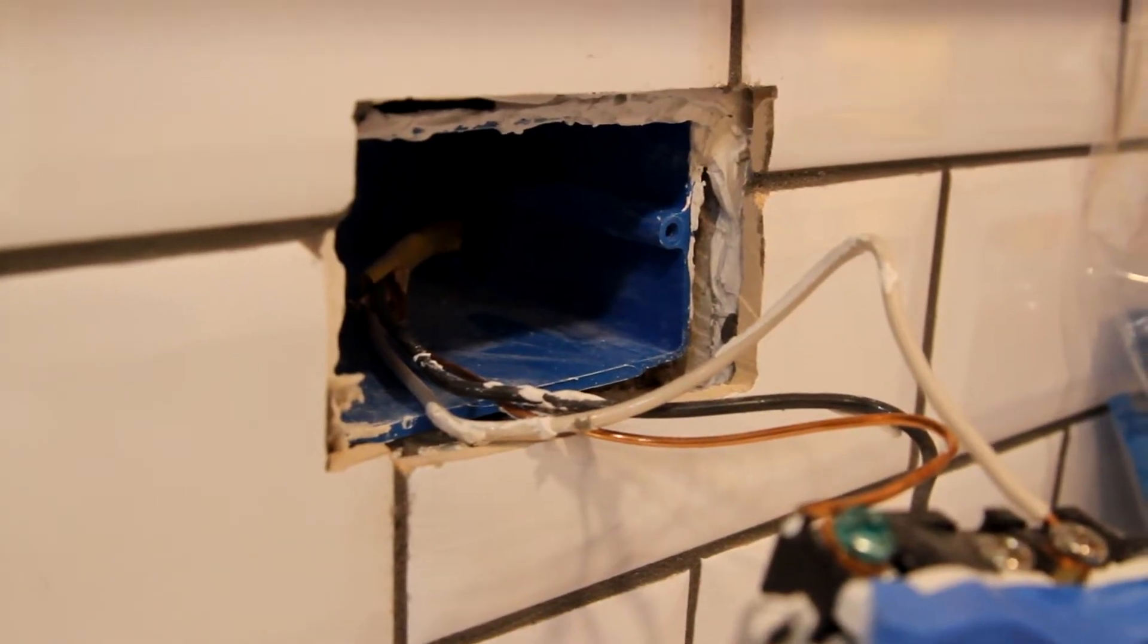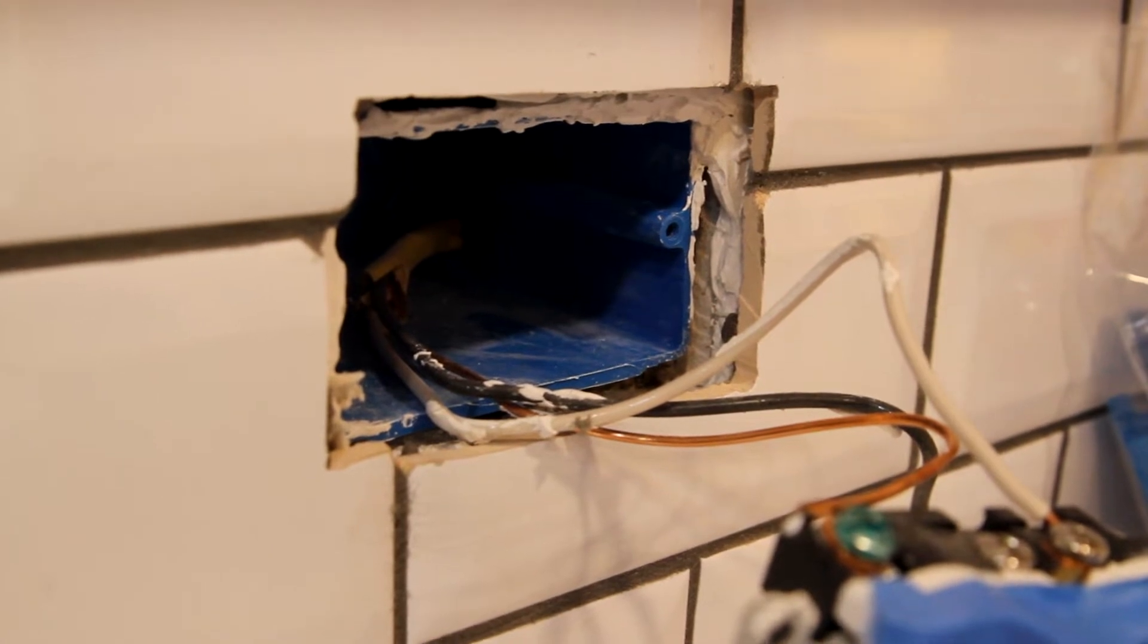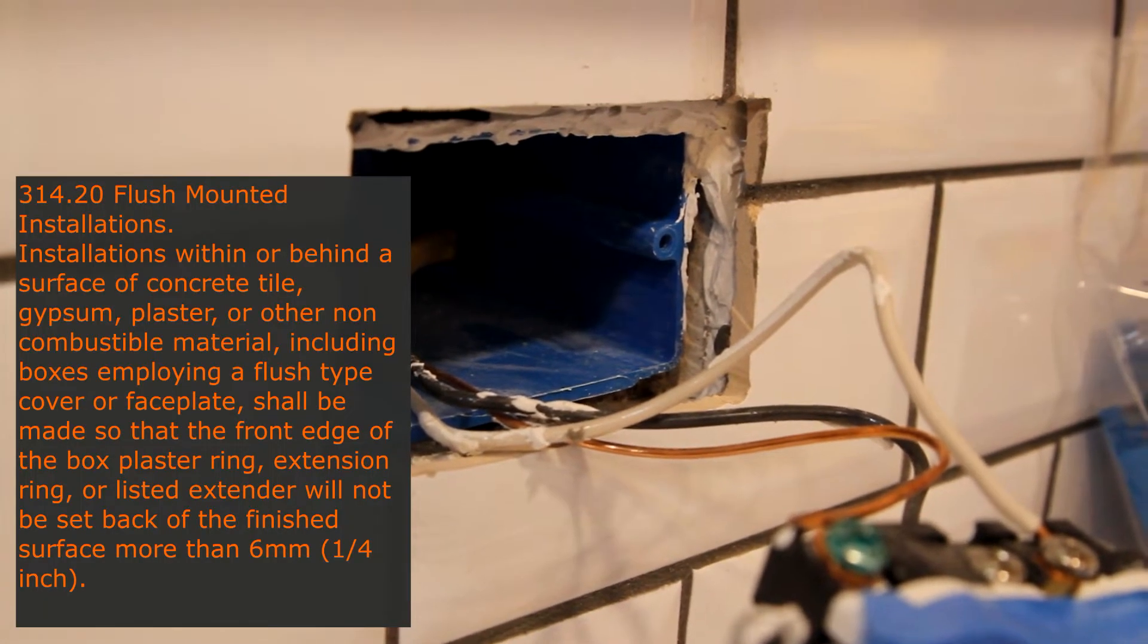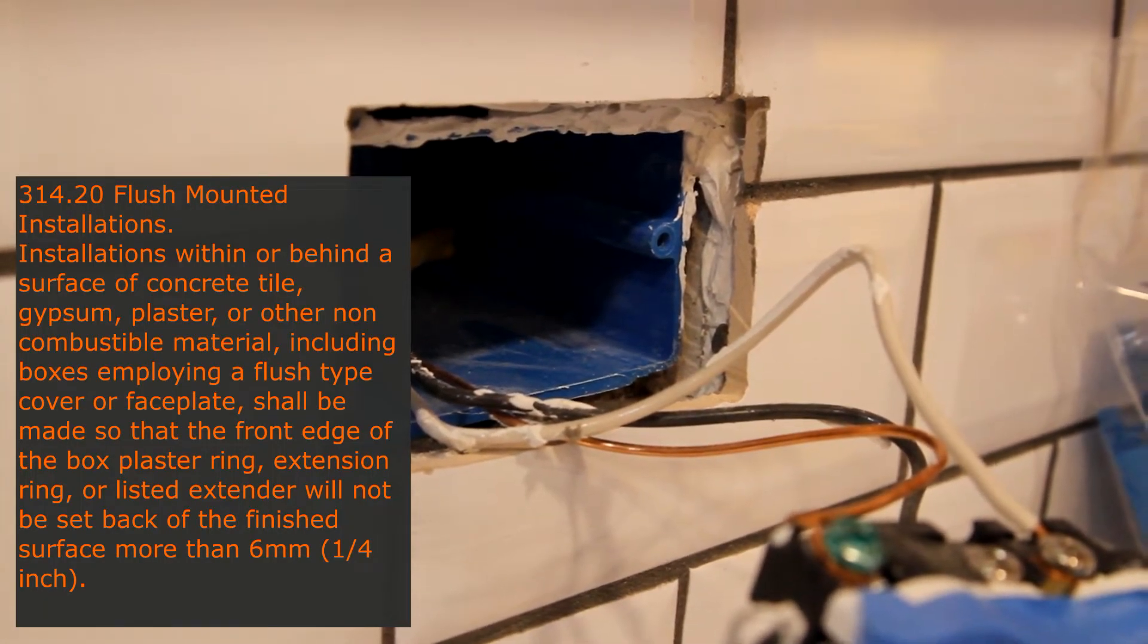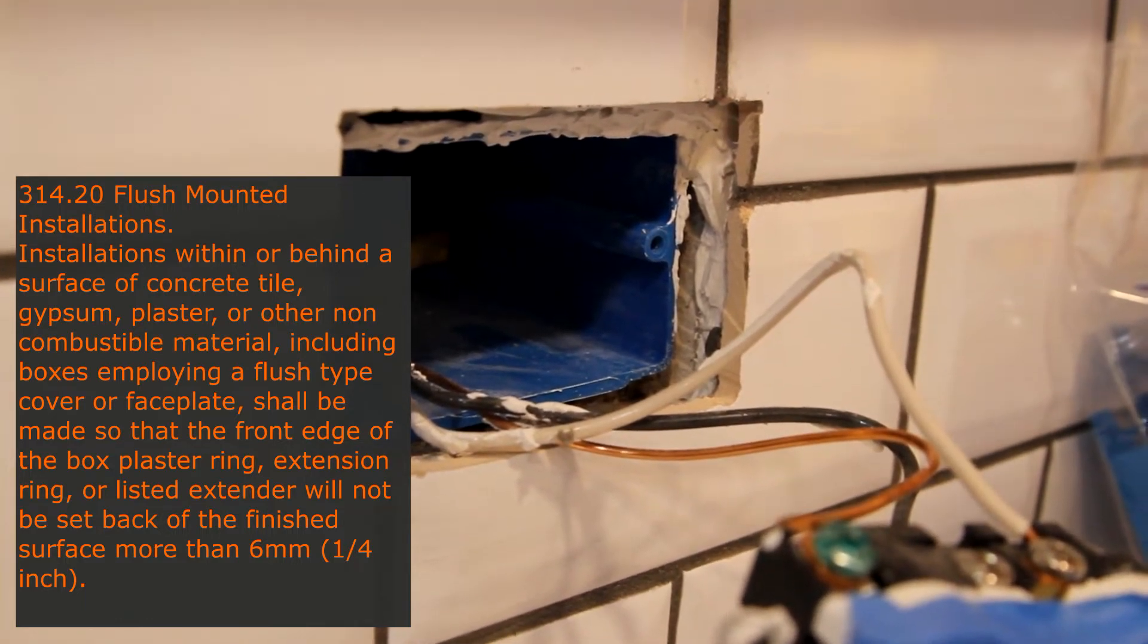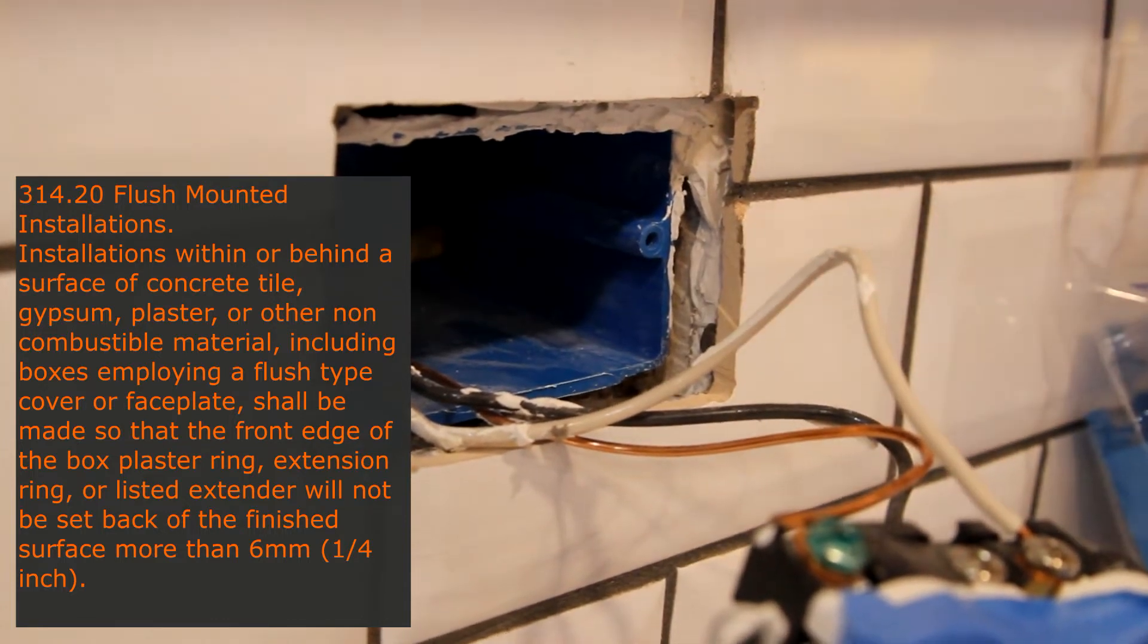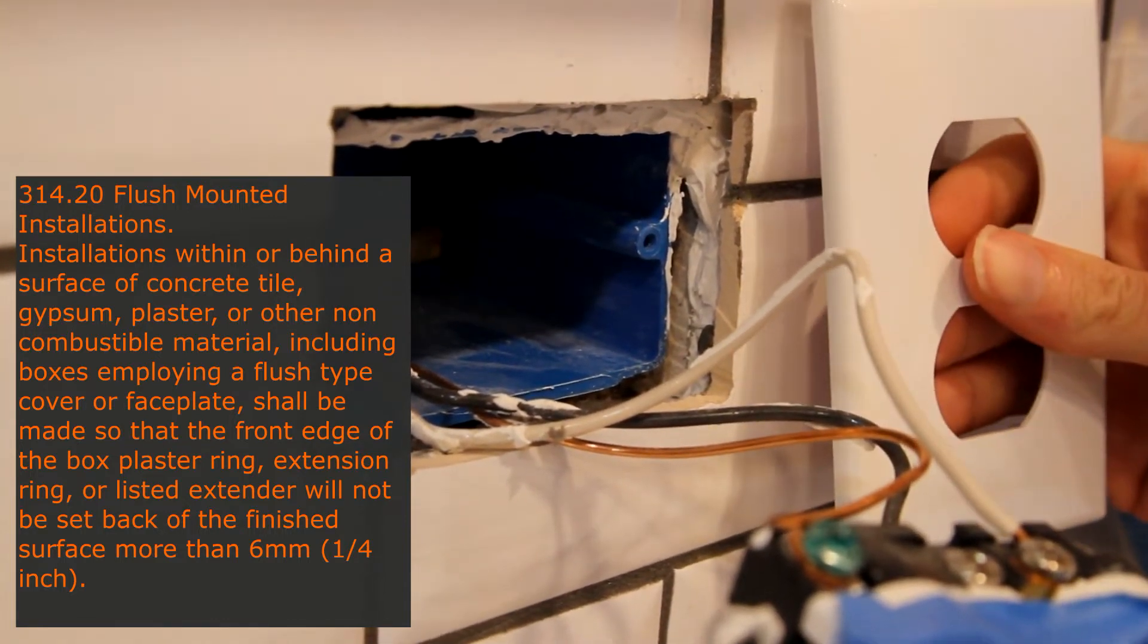So right here we're looking at what is probably the most common National Electrical Code violation. NEC code 314.20 says that you can have no more than one quarter of an inch between this box and this outer surface, which in this case would be the outlet box cover.